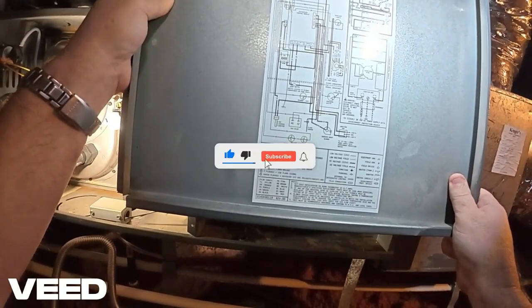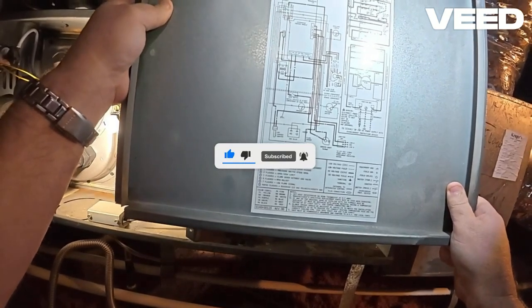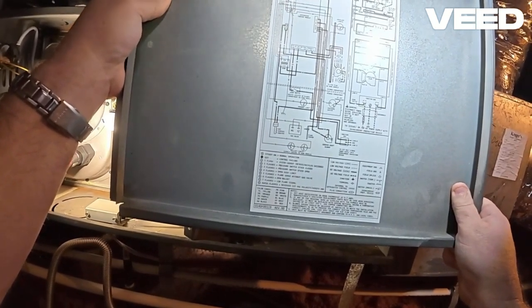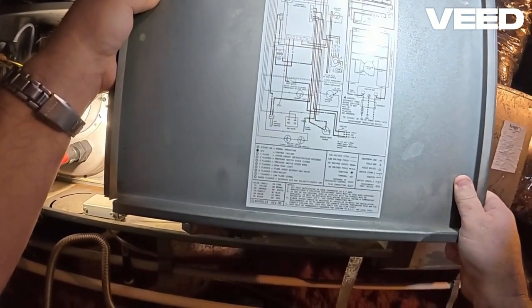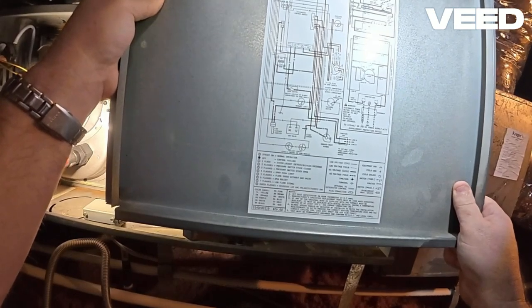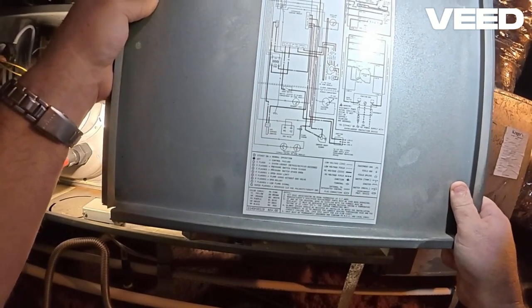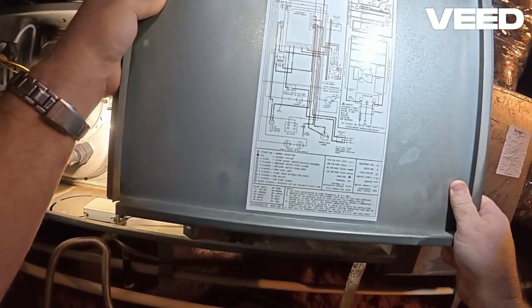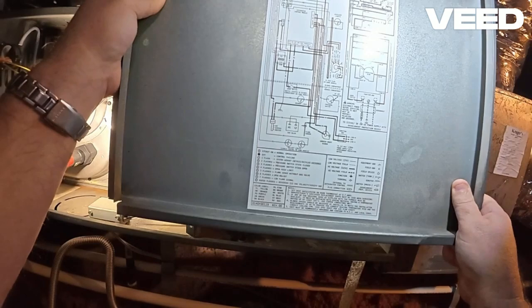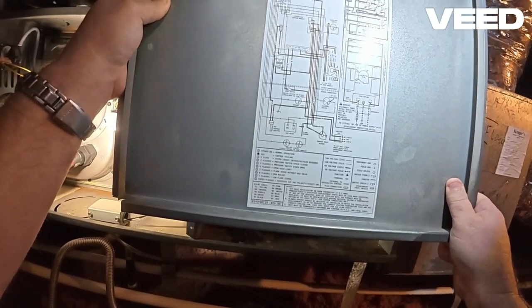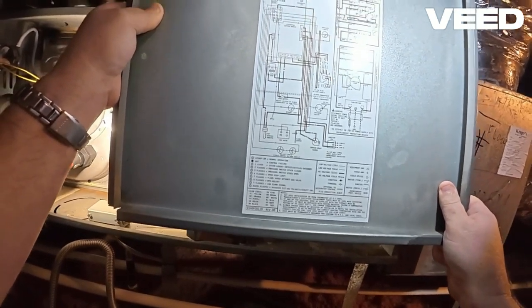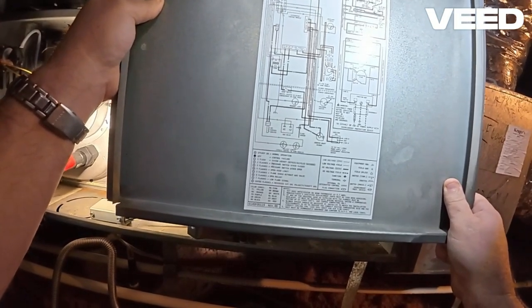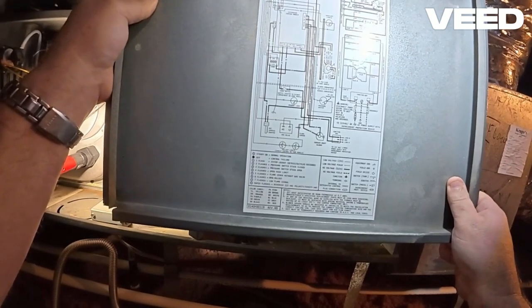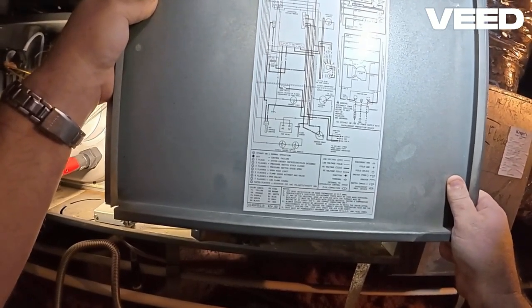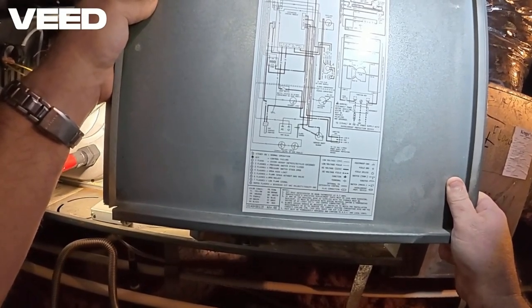So in this unit, a steady on means normal operation. If it's off, it means a control failure. So that could be a tripped breaker, the power's turned off. There's a 3 or 5 amp fuse on the control board itself that could be burnt out. And then we have one flash. So one flash in this case means it's in system lockout. The systems will typically try and restart 3 times, and after that they will go into a lockout.